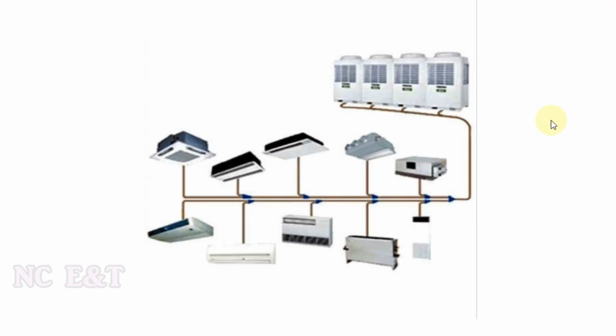VRF system looks similar to the split AC, but there are certain special characteristics we cannot get in the split AC. Number one, different numbers and different types of indoor units can be connected through a single piping network to an outdoor unit or a group of outdoor units, and we call it one circuit of the VRF system.